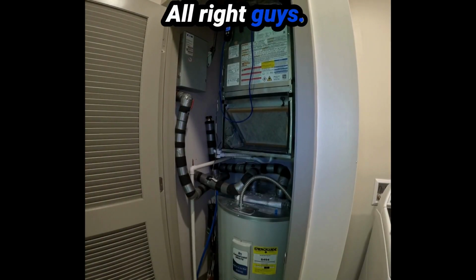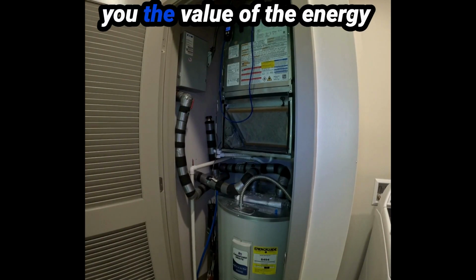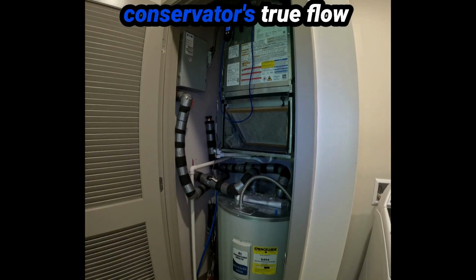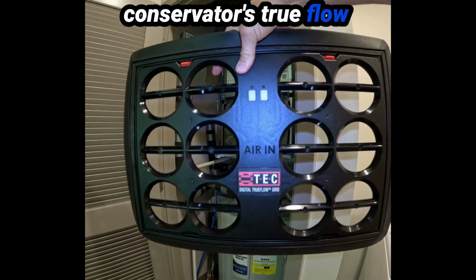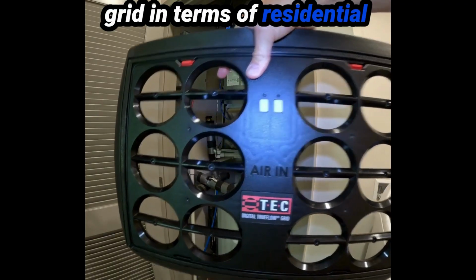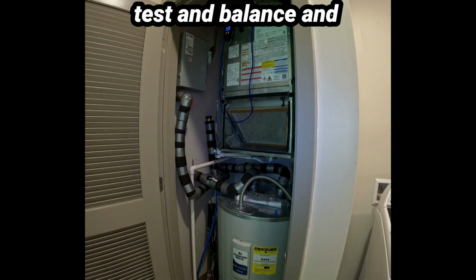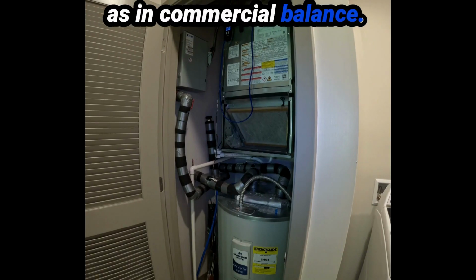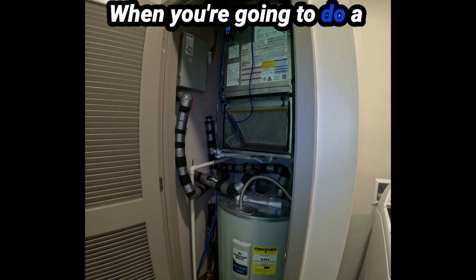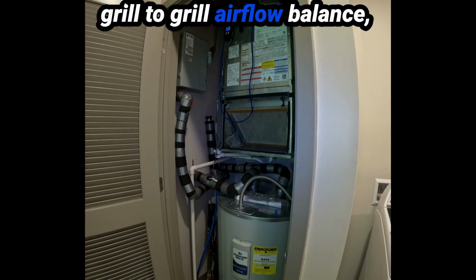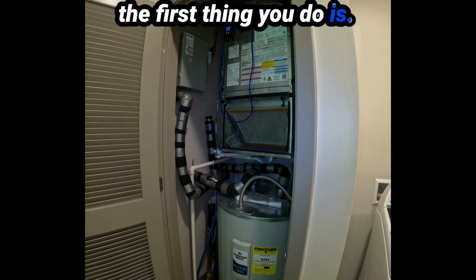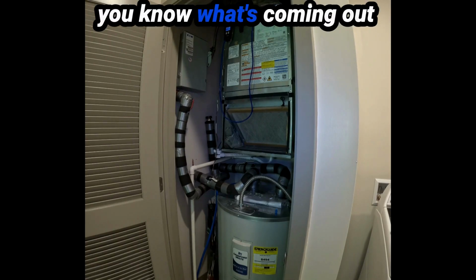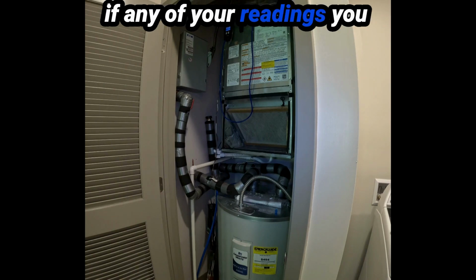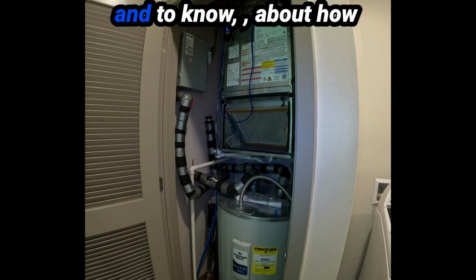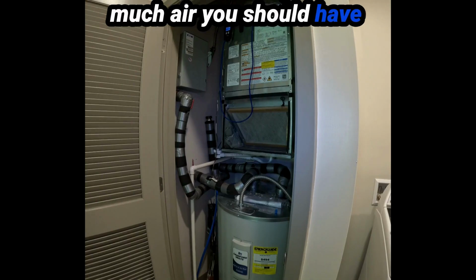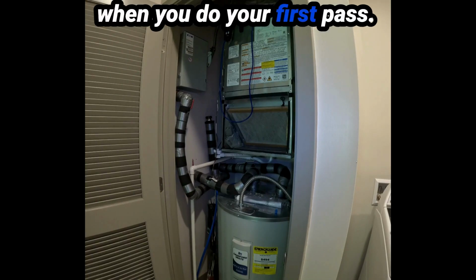All right, guys. Today I'm going to be showing you the value of the Energy Conservatory's TrueFlow grid in terms of residential test and balance. In residential test and balance, as in commercial balance, when you're going to do a grill-to-grill airflow balance, the first thing you do is get your total airflow, so you know what's coming out of the box. You can use it for comparison and to know about how much air you should have coming out of the registers when you do your first pass.